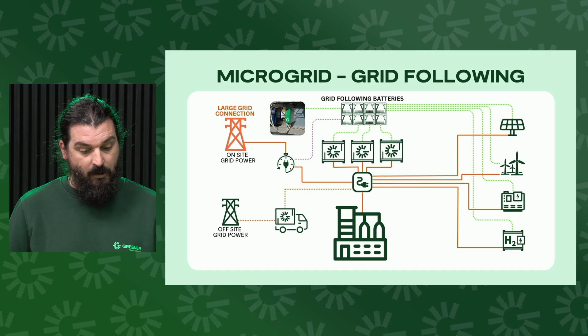Why is that? The main reason for that is that if we're in grid forming mode, we use the frequency to control the entire grid. And if we are connected to the national grid, well, with our 750 kilowatts, we're going to do absolutely nothing in changing the frequency against the national grid, which is how many gigawatts of energy there. So we just monitor the power flow and then add or subtract power flow to respect the limits which are on the grid connection that we're monitoring right there.